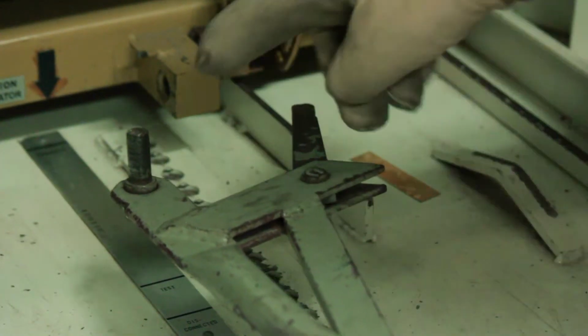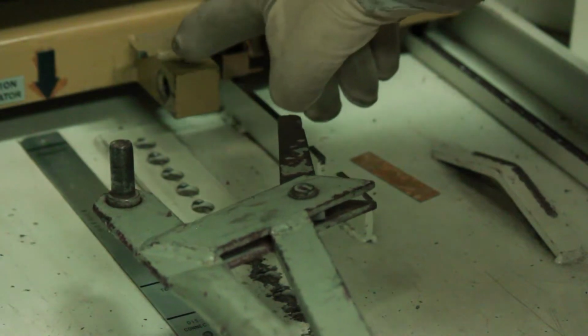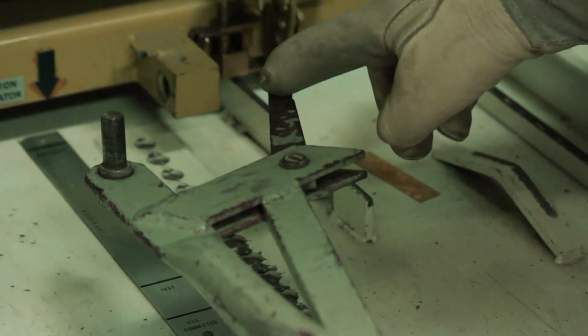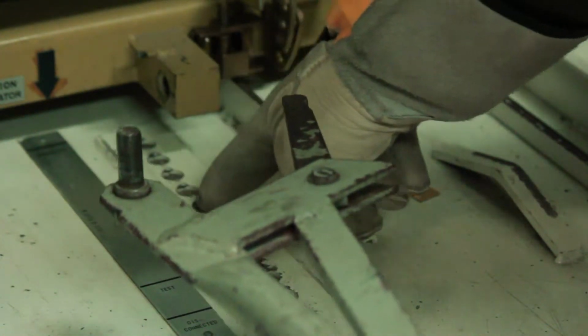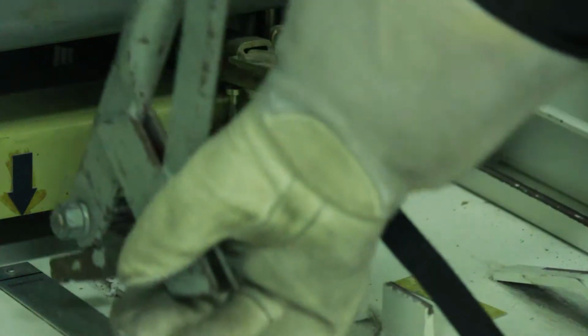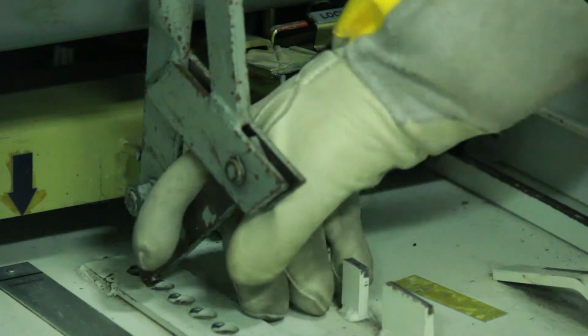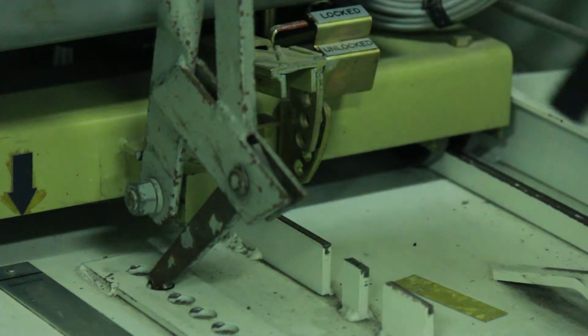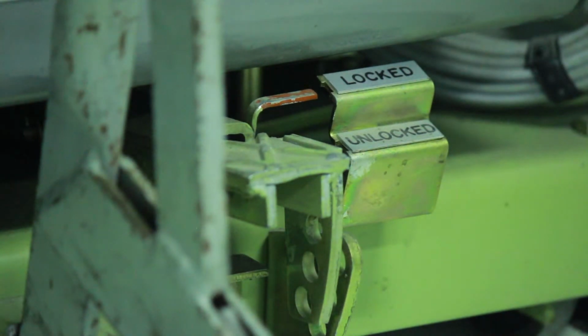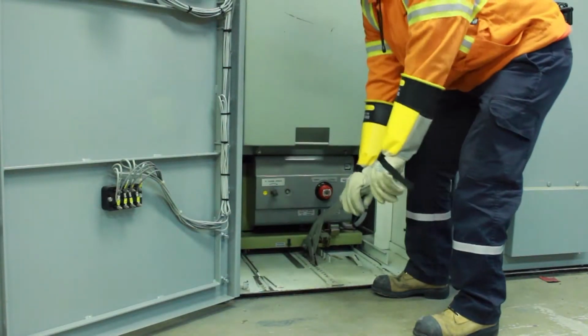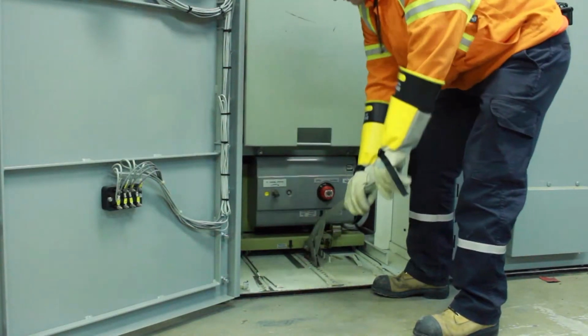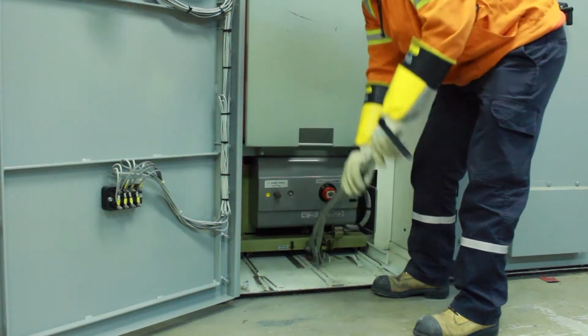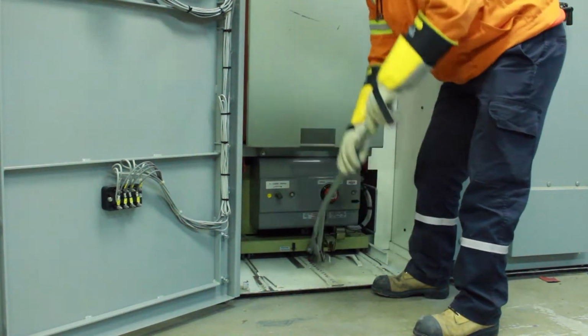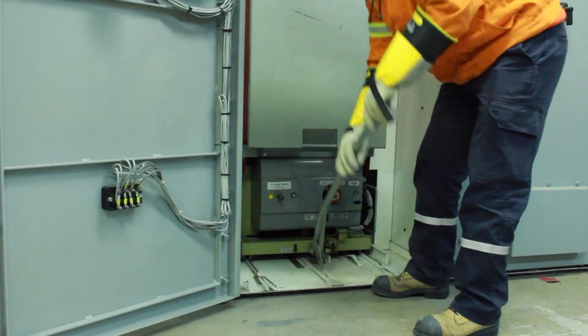The racking operating handle should be inserted to its proper position in order to correctly disconnect the breaker from the bus. Once the racking handle is in its proper position, and by using your foot, depress the pedal interlock to enable you to rack the breaker off the bus. As you rack the breaker off the bus, you will hear an arcing, sizzling sound. Continue to rack the breaker without hesitation.